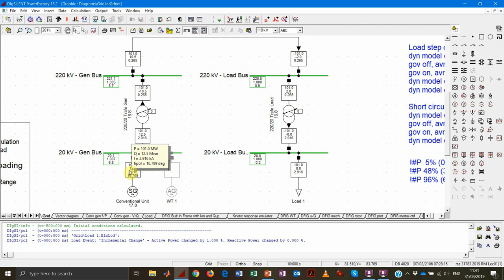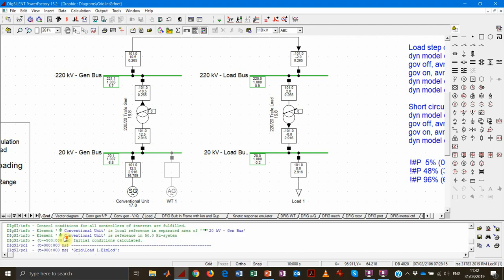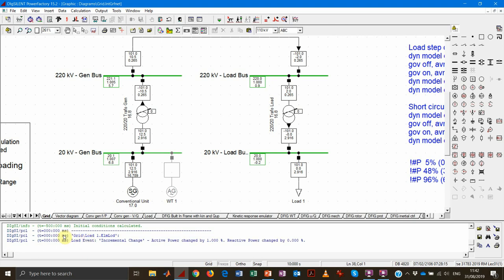Notably, the reactive power increased a little bit as well. Why? Because we increased the active power flowing through the system, which increased the current flowing in the system, which in turn increased the reactive power losses on the line and transformer. This value slightly increased as a consequence. We can also see in the event log that PowerFactory reports the load flow ran fine and that we had an event at t=0 — a 1% active power increase on load 1.